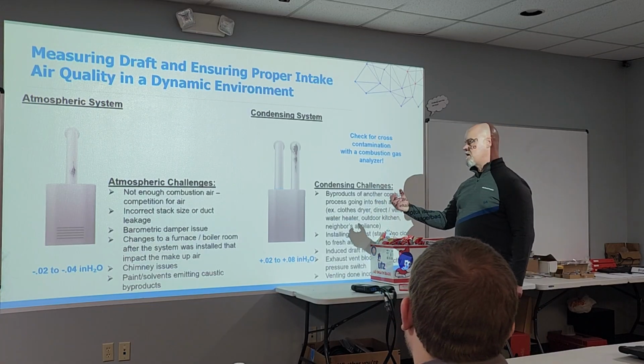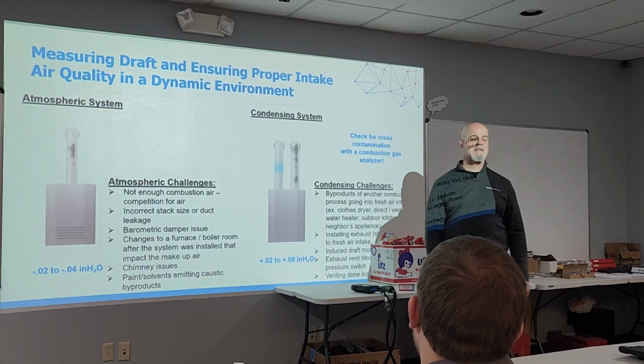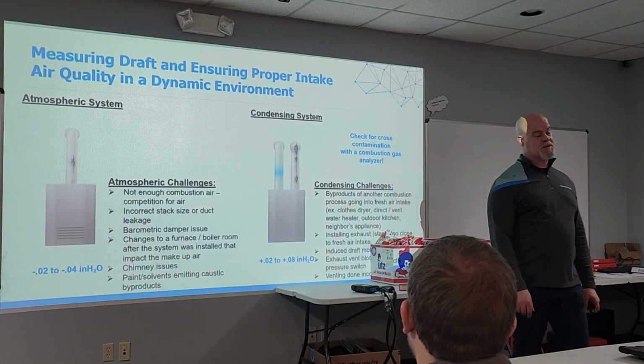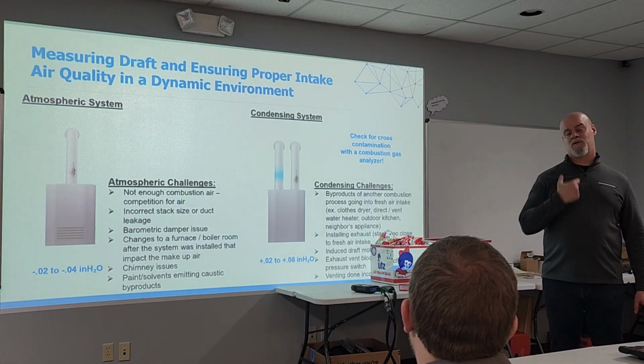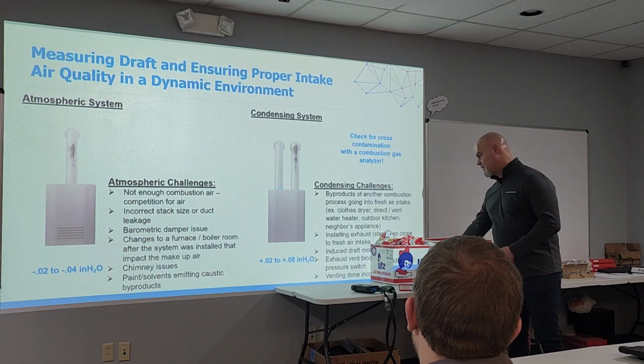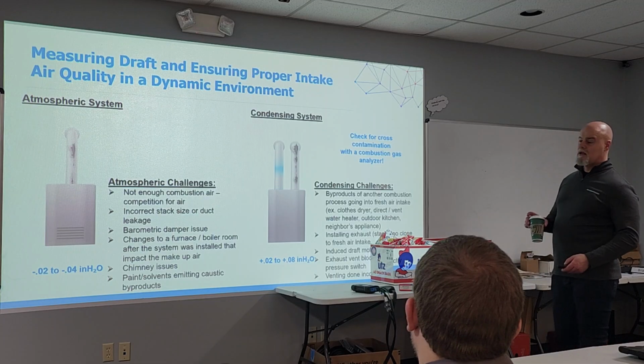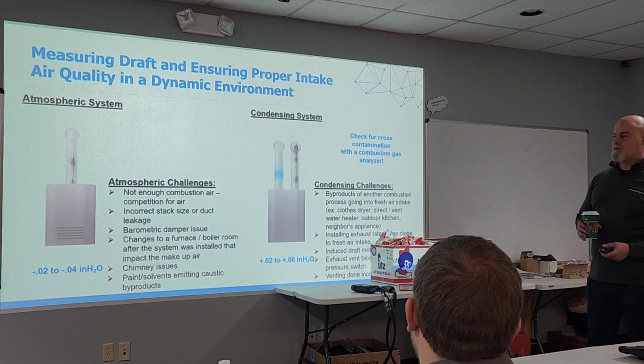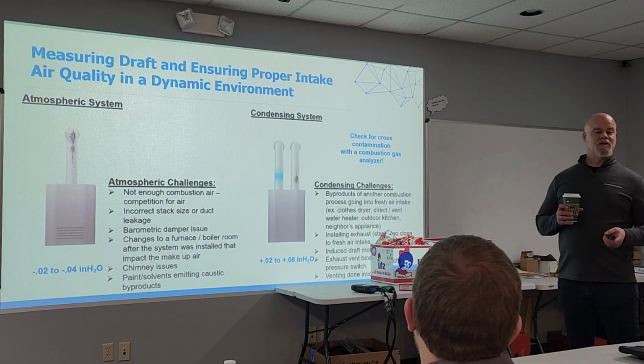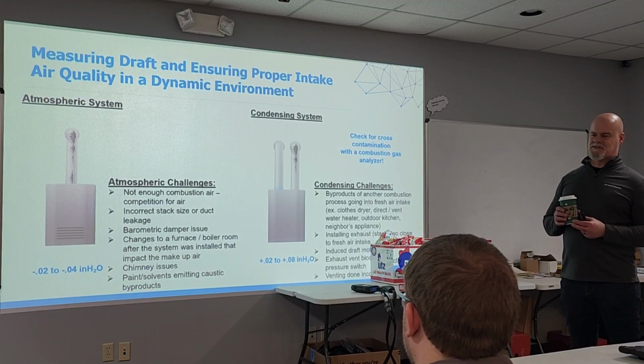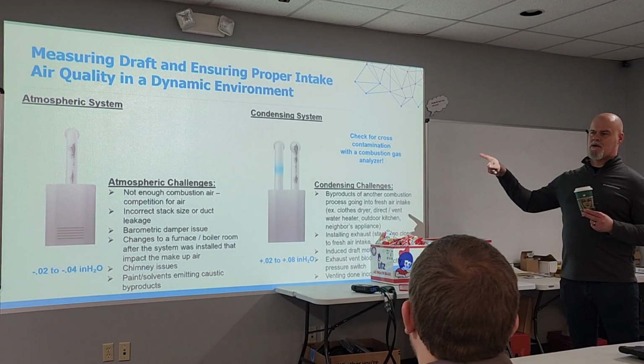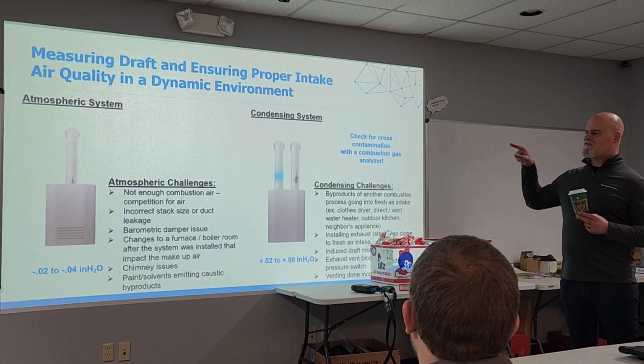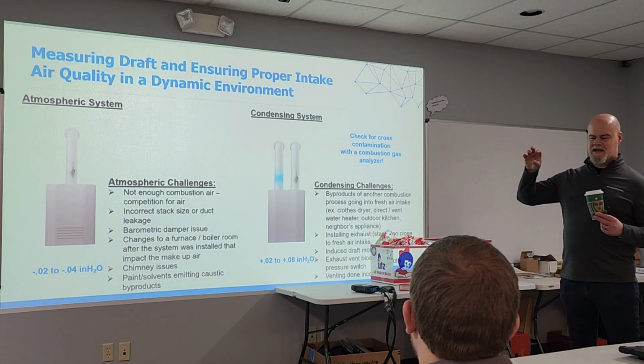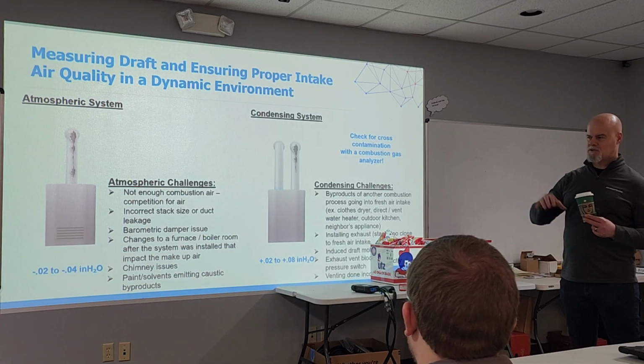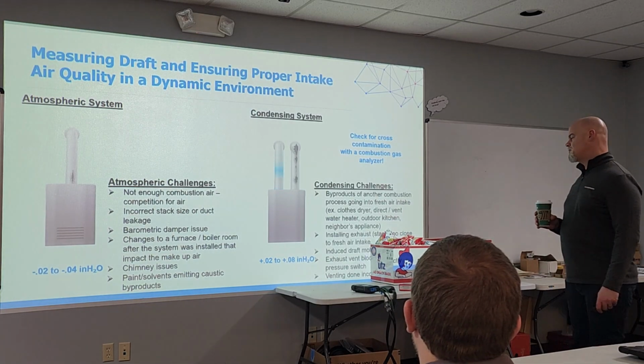So as it gets pulled down in here and it gets into the mechanicals, it's going to start to eat them and age them prematurely, which is a problem. Again, it's like sipping Drano every day. We don't want to do that, okay? So very, very important that we put that probe in there and we make sure we have 20.9. I would check my draft, obviously revisit, but I would always go out, unless it's on a roof, always go out and verify that there are no nests or nothing is in there, especially in the sidewall discharge, okay? So just point of fact.